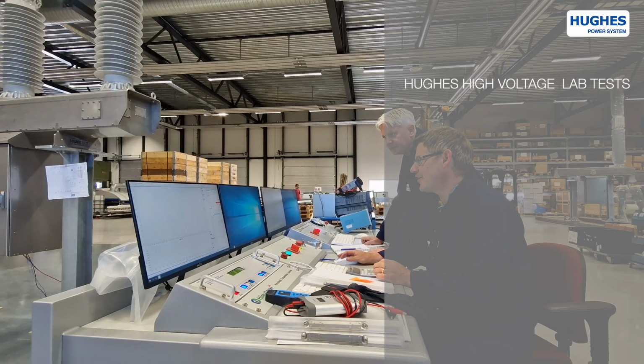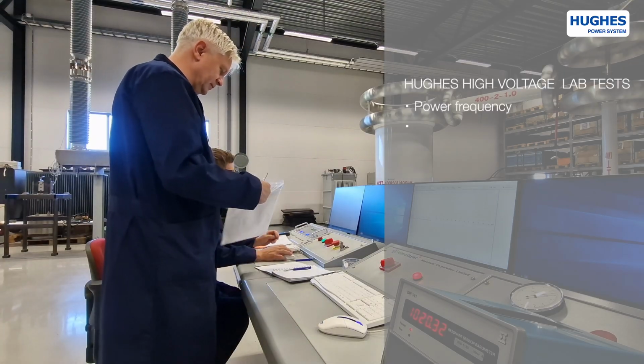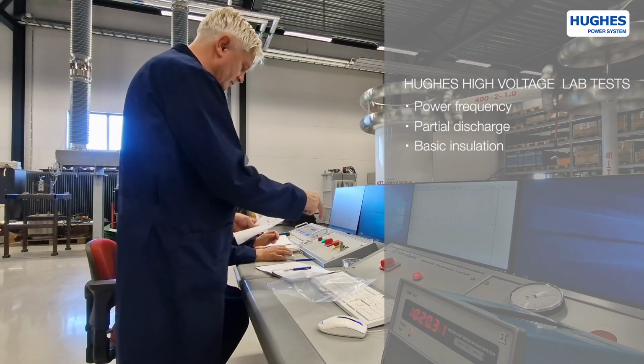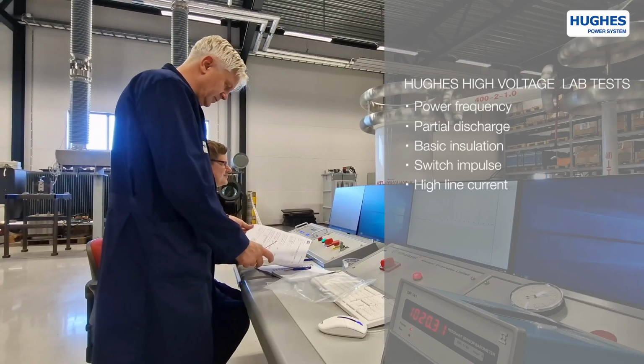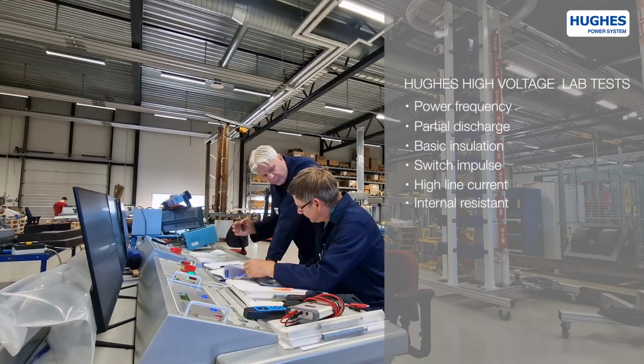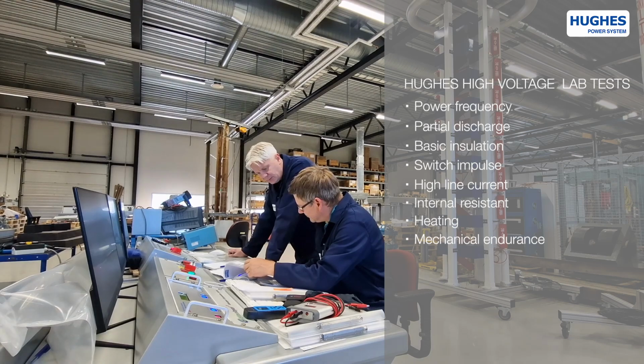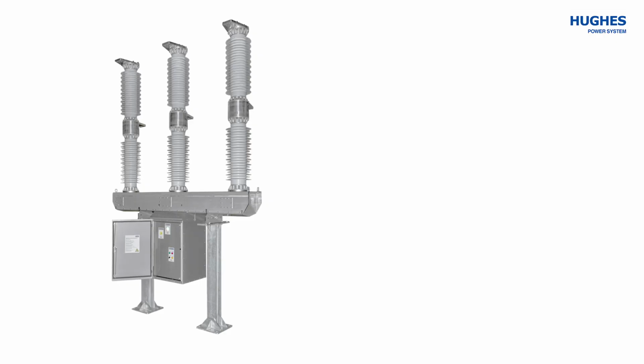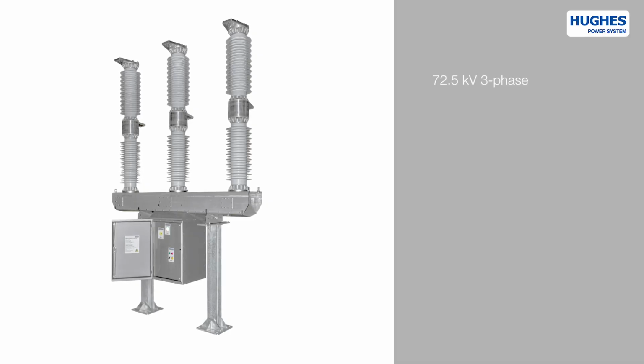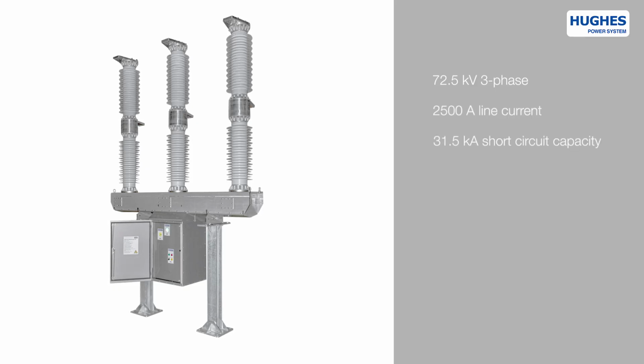The following tests are performed on OVX723: power frequency, partial discharge, basic insulation, switch impulse, high line current, internal resistance, heating, mechanical test, X-ray emission, high-speed operation video, thermographic tests. The product has the following main characteristics: voltage class 72.5 kV 3-phase, 2500 A line current and 31.5 kA short circuit for 3 seconds.